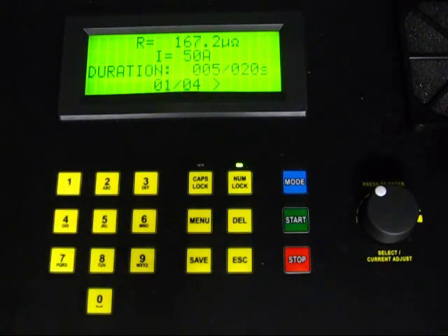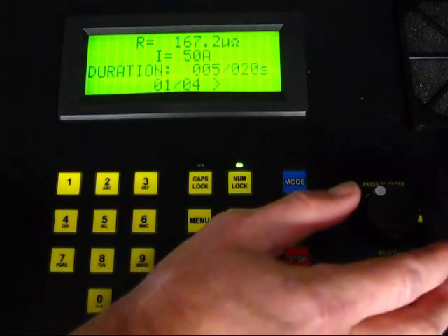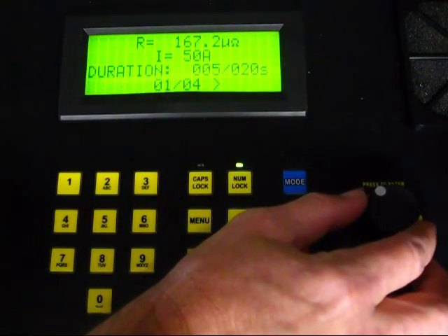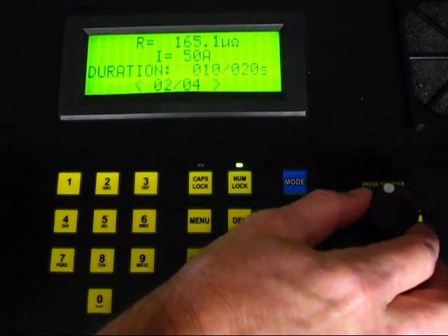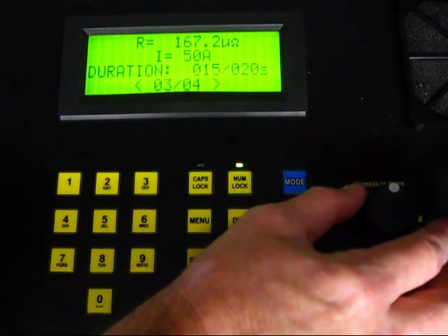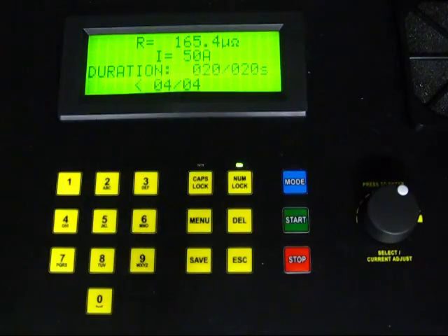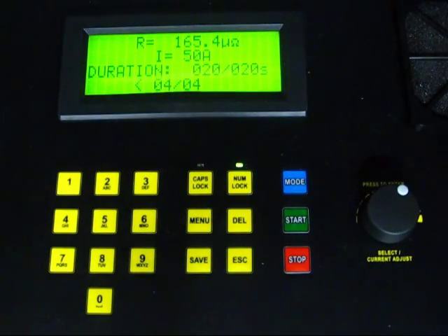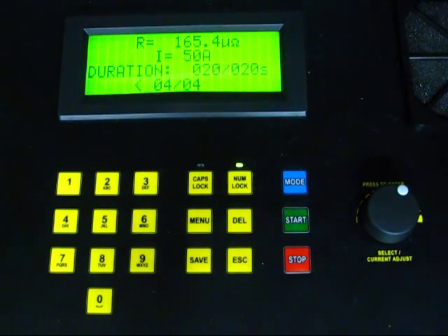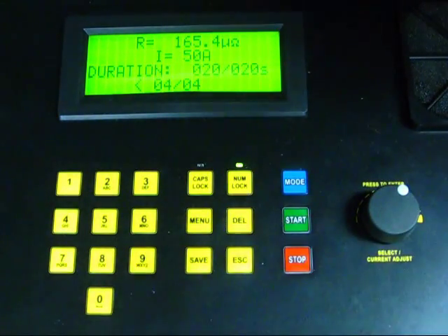To see the remaining measurements, turn the rotary knob to step through the test results. The final result is shown as 165.4 micro-ohms at the 20 second mark.